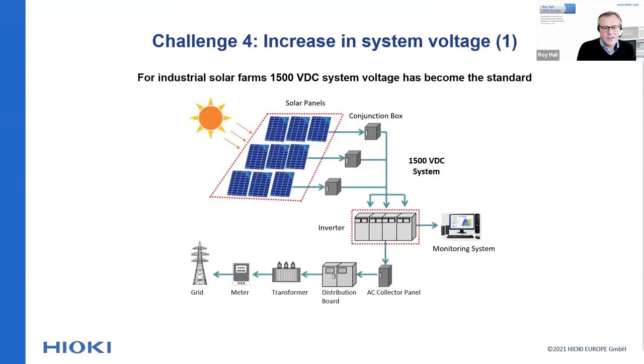The fourth and last challenge that I would like to mention is the increase in system voltage. We have seen different applications where the system voltage and especially the DC voltage is increasing. The first one being the industrial solar farms. We see now that the standard voltage is around 1500 volts DC. And that is producing some issues because there are some changes in regulations, which I will mention later in this presentation. The reason why they increase the voltage is that they want to have more efficiency and more power out of a solar farm, and in that way be able to reduce the price of solar energy.